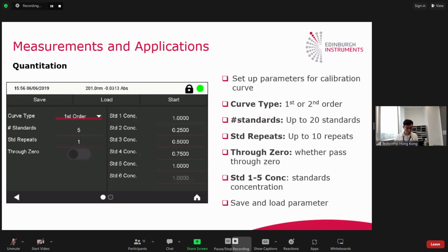For the quantitation, you need to build the calibration curve. So here is the screen of your settings for the calibration curve. You can first select the curve type: is it the first order or the second order? The first order will be a linear curve. The second order will be a parabolic curve. Then you can set up the number of standard points in your calibration curve, or the number of times you want to repeat the standard points, and you can also choose whether to force the calibration curve to pass through 0.